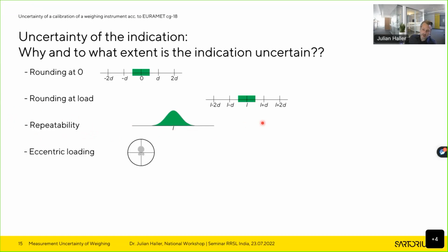Next thing to be considered is eccentricity, or eccentric loading. Of course, if you calibrate a balance, I think everybody will do this intuitively, you should place the load in the middle. But for some loads, it is just not possible to put the weights in the middle of the weighing pan. For example, if you have some test load like, let's say, 130 grams, 120, 10 grams, it is just physically not possible to put them into the middle of the weighing pan.